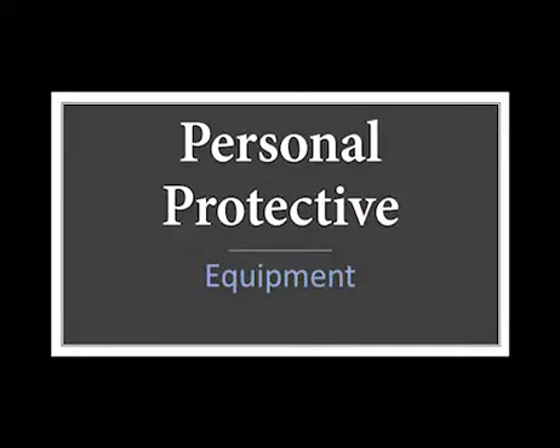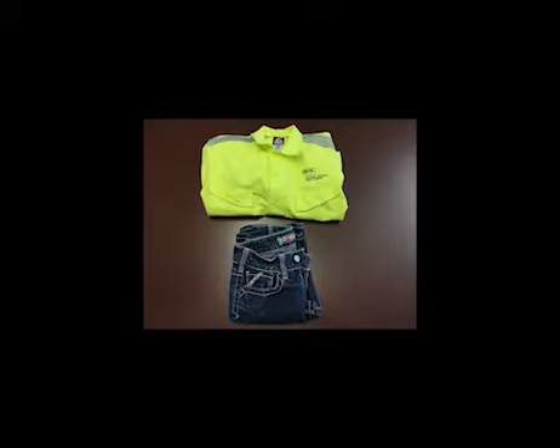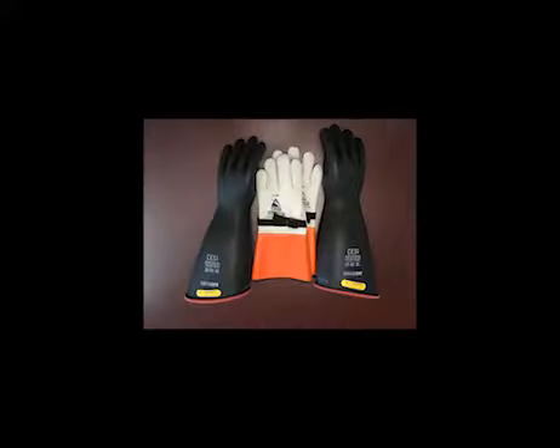PPE requirements. There is a variety of PPE that must be worn when working at OMPA substations. FR clothing with a minimum hazard risk category of 2 or 8 calories per centimeter squared, hard hats, safety glasses, and steel toe or composite shoes are required to be worn by contractors at all OMPA substations.